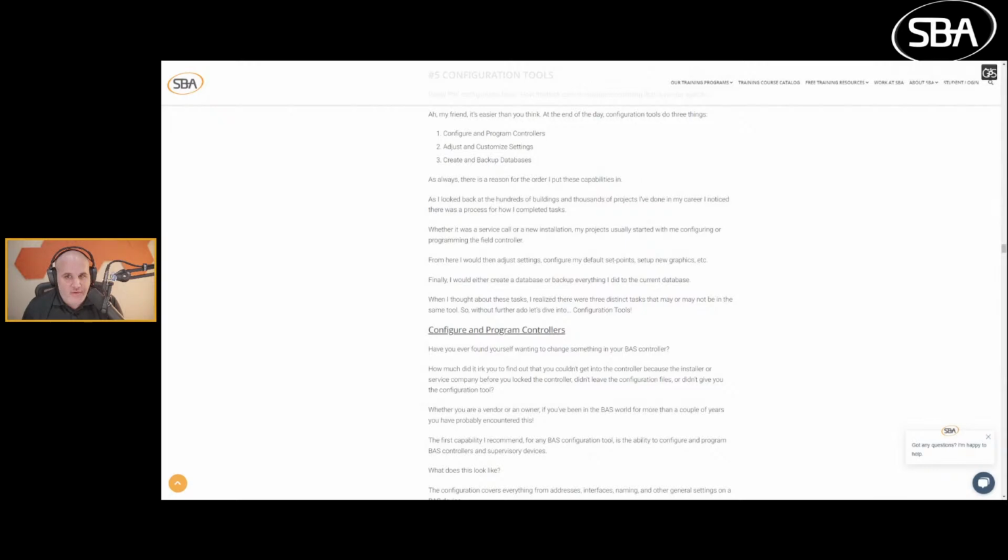if you do anything from this podcast, anything at all, when you develop a standard or you do an RFP, RFQ, or you do some sort of engagement for a building automation system, please put in the spec or whatever document you use that the contractor is required to provide you open administrative licenses to the software for whatever software is required for the building automation system you purchase. And here's why. If you ever want to use a different contractor, you've got the software. If you ever want to do something yourself, you've got the software.